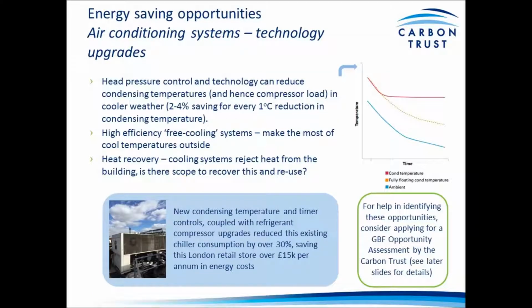If you are looking at technology upgrades, AC systems often tend to be less well understood than other HVAC systems unless you work on them regularly. So I'd recommend taking specialist advice unless you are familiar with the technologies and efficiency upgrades possible. Some options may include head pressure controls, which reduce the external condensing temperatures and hence the compressor load when it's cooler outside. Again, a 2 to 4% saving with every 1 degree C drop in condensing temperature.